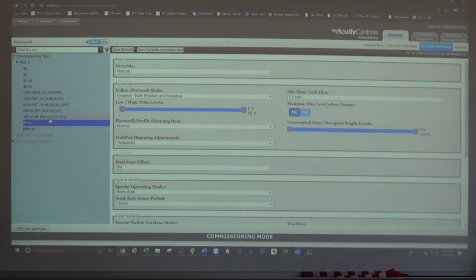Okay, so this is a power pack that is dimming, right? These have all the dimming options, and it's following the photocell. Like I said before, the easy way to turn off a photocell if you're having problems with it, or you don't need it anymore, is to unplug it, then plug it back in when you need it. If you need to change the setting digitally, like on the networked ones out in your commons, you can go under photocell follow mode, hit disabled, save and apply, and you're done.